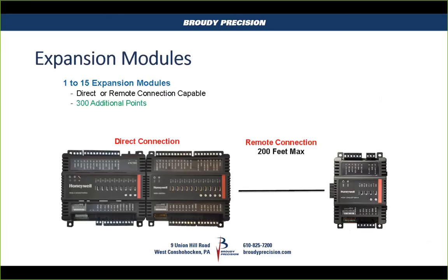So you have up to 15 expansion modules, and if you ask what protocol they're using, it's actually panel bus that's being used for communicating with these modules. And currently it's just these two modules, the small and the large. Down the road, they are going to expand it to be able to have the standard panel bus devices like you have with the Eagle controller or with an XL800 type controller.